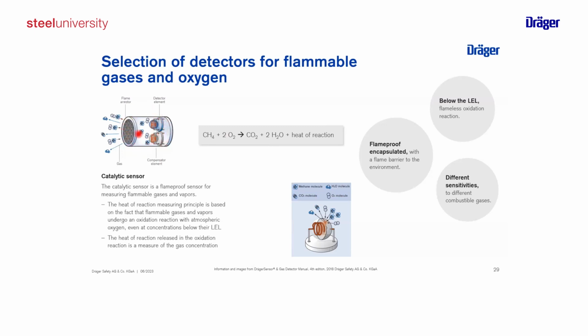As we have a combustion process here, we need to secure that this combustion is limited to the sensor. So, for example, the sensor is typically designed as a flame-proof or explosion-proof enclosure with a flame arrestor in front. Like the EC sensors, we always need oxygen, otherwise we have no combustion.